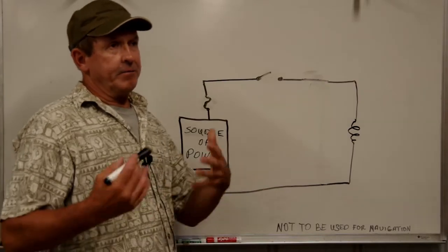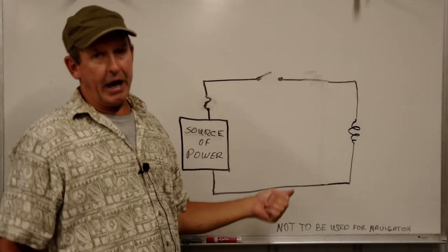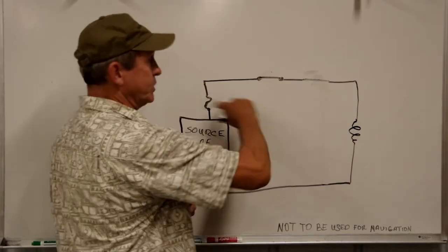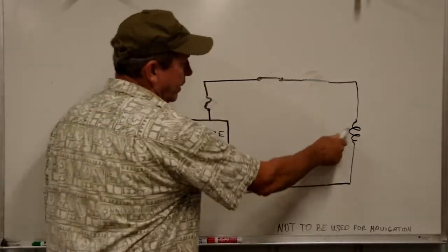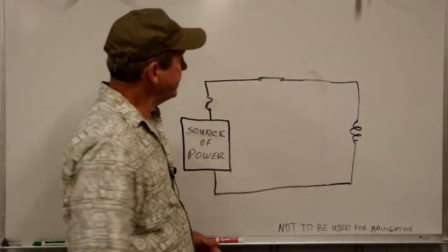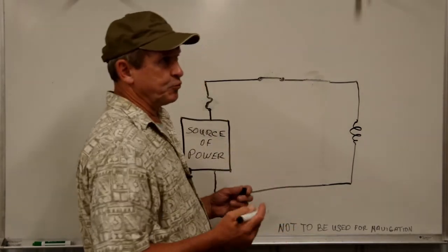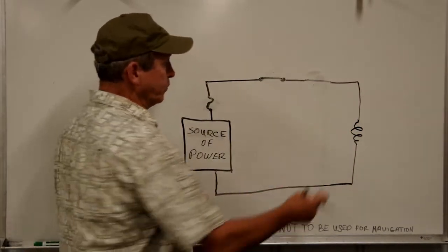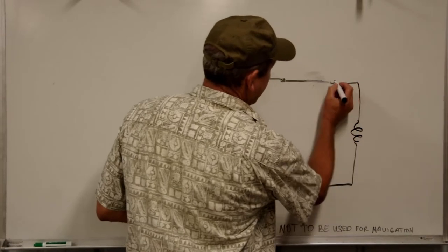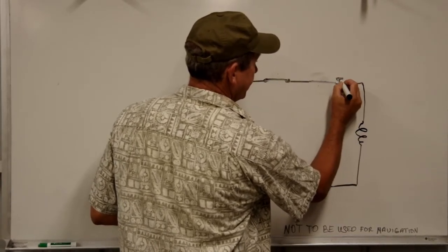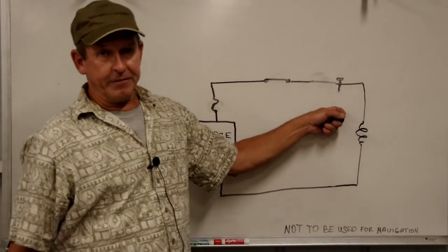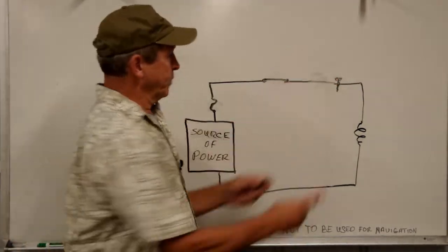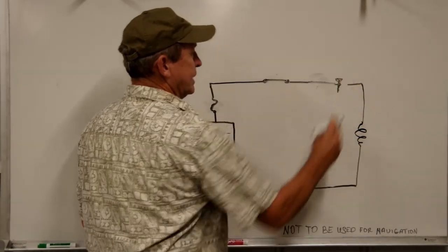If we have an unwanted open, something has gone into the circuit and broken it. For instance, we close our switch, current begins to flow, we're powering our device and getting the work we want done. An actual case just recently: we had a light circuit — the light was not coming on, we had no power to the light. Interestingly, we found a screw that secured the light fixture to the bulkhead. Our light was not energized, but our screw was.